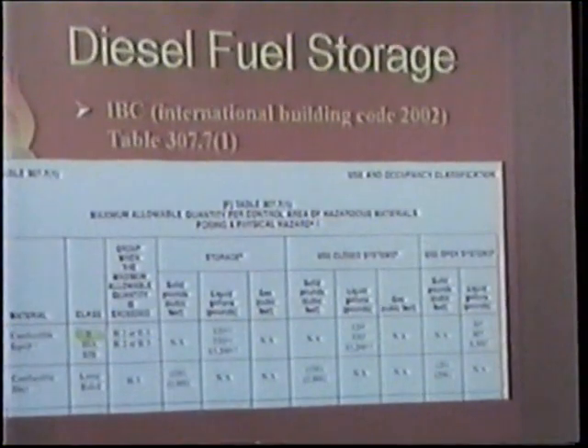This is a storage issue, and I bring it up because we keep seeing diesel fuel tanks in buildings where the tank is larger than the area in which it's supposed to be. So what we have is, if you look here, on the combustible liquids, class 2 is diesel fuel, 120 gallons right there in a closed space, non-sprinkler. Now if you put it in a sprinklered space, you can go up to 240 gallons.